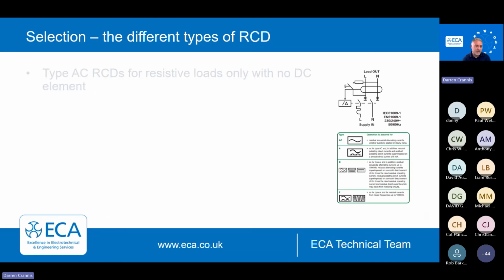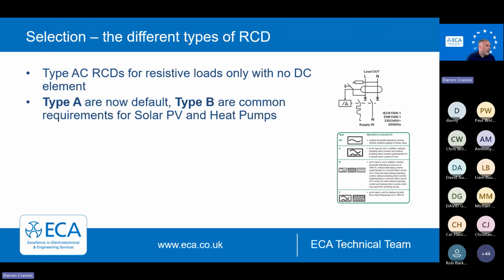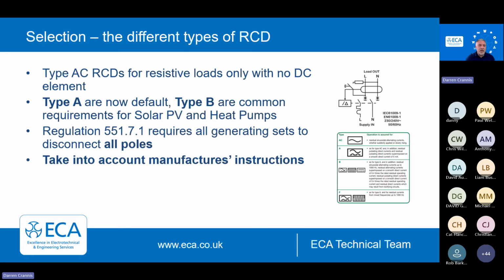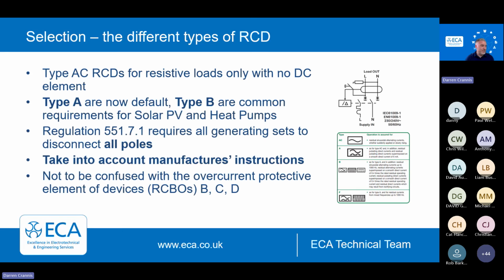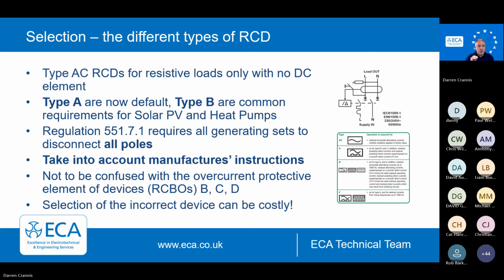So the different types of RCD, we highlighted this earlier. Type ACs, we've had them for decades. Great on purely resistive loads. So that might be immersion heaters, or direct panel heaters, linear loads. Really now they are a thing of the past. Type A, with that 6 milliamp threshold, they're a bit more tolerant to DC noise, which is common.